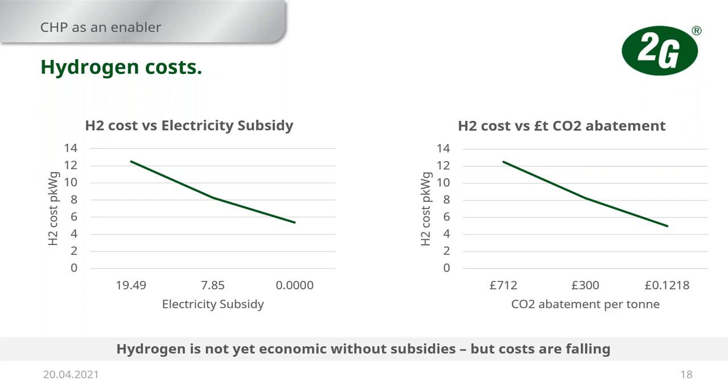Yeah, good. So next question, I think it's related. When you switch over from natural gas to hydrogen, what effect does that have on the output from the engine? Normally, if we've got the engine set up to be running 100% hydrogen, then we switch to natural gas. It's what we call a blending line. It's something we developed for the biogas industry, where sometimes the biogas anaerobic digesters didn't have enough biogas, so they still wanted the heat to run the anaerobic digesters. So we developed this technology to run natural gas into biogas for the blending to keep the engines running. If we've set the engine up to run 100% hydrogen, we wouldn't go higher than the power output of the hydrogen. So if we've got our 1 megawatt engine with the hydrogen injection system on it, configured to run at 750 kilowatts on hydrogen, if you go on to natural gas, we'll still run it at 750 kilowatts. We won't bother increasing the power output, otherwise we have to change the compression ratios and everything else in the engine.